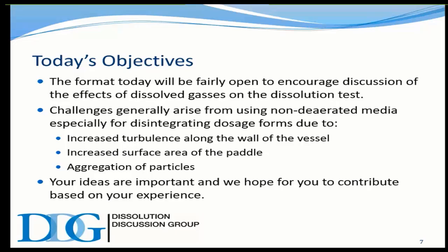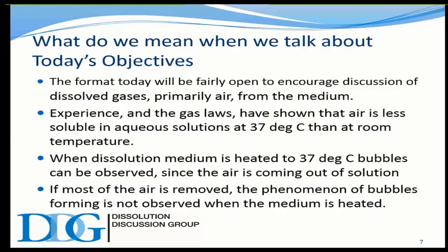Another area with air is aggregation of particles. Air, when it's in contact with a solid particle, often will attach to it and raise it to the surface and may cause other issues with the dissolution rate, changing it from what would be a situation with no interference. Now it could have a drastic effect on the dissolution test results. Anyway, we look forward to your ideas as we're moving through these topics.